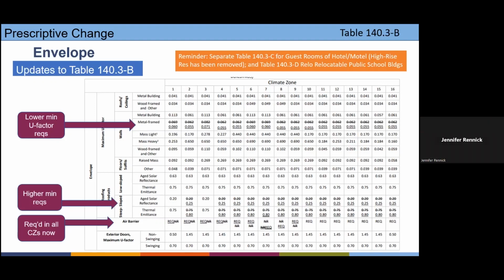And then the climate zones that are more mild, like climate zone 3, that's the mildest one now. It was 0.071. That one only needs like an R8. So like 2 inches of insulation. So if you're going to use metal stud walls, you pretty much are looking at some kind of insulated paneling system or other means to get that exterior insulation.